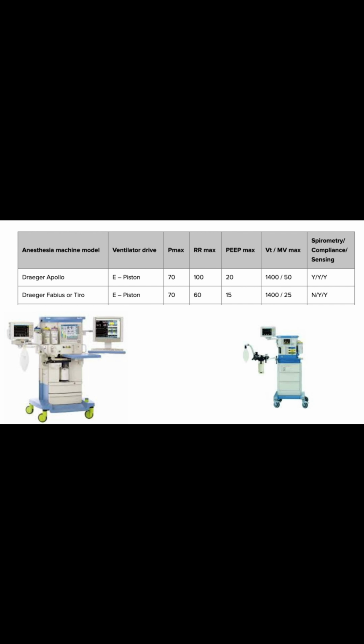So we have Draeger Apollos and Draeger Fabius Tiros as our two that we have available to use. These are the specs on them, but actually what we found is our Fabius Tiros actually have a maximum PEEP of 20. So they're able to deliver quite a lot of support. You can see tidal volumes max there, and inspiratory pressure max is quite high. Not as high as ICU ventilators, but still a decent amount of support that's available. We'll be favoring the Fabius Tiros because of the smaller footprint, but we will likely have to use some of our Apollo machines as well.